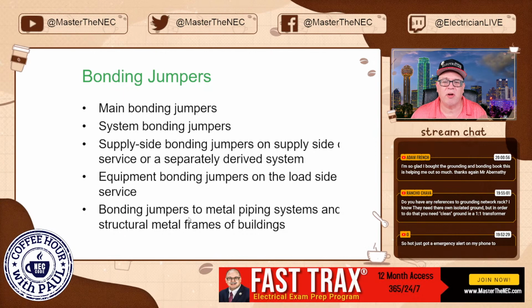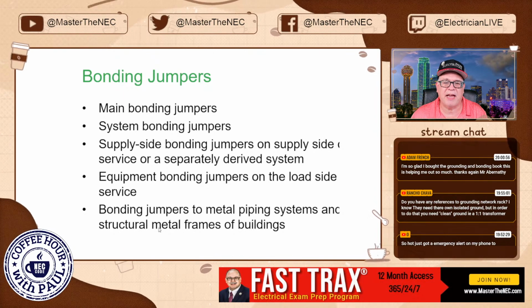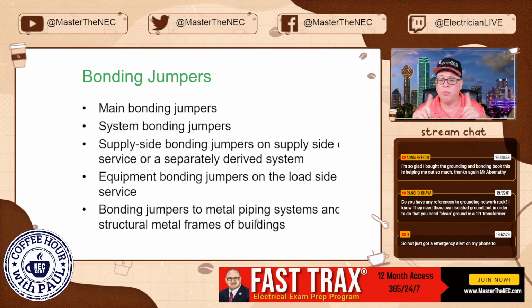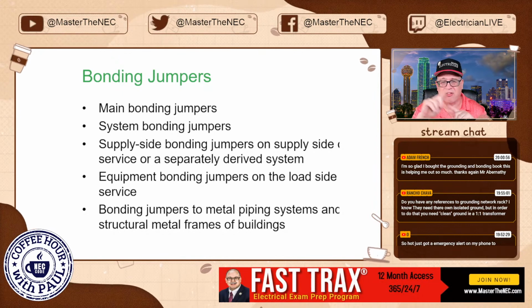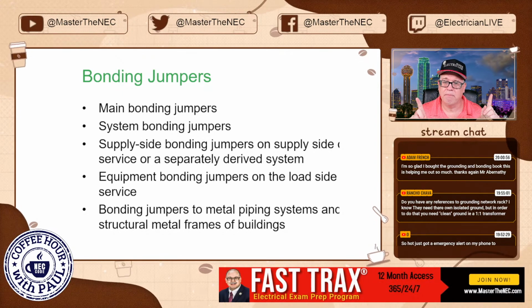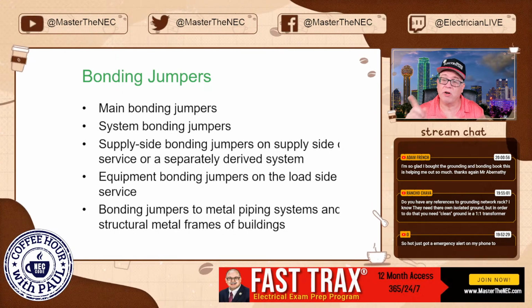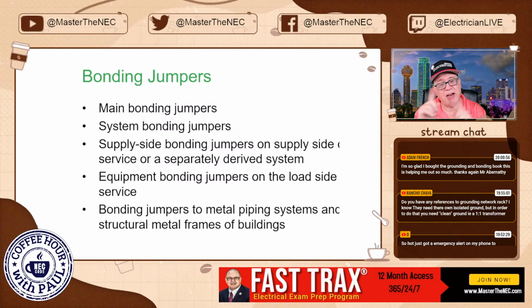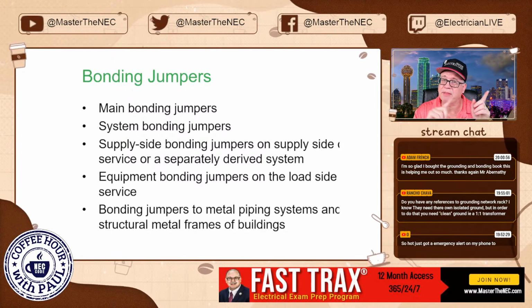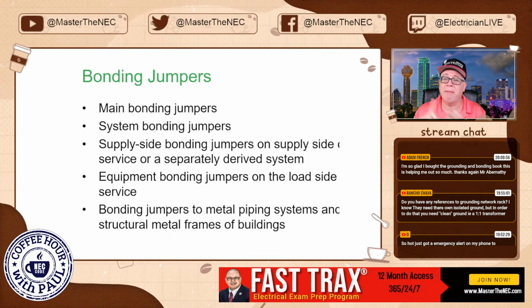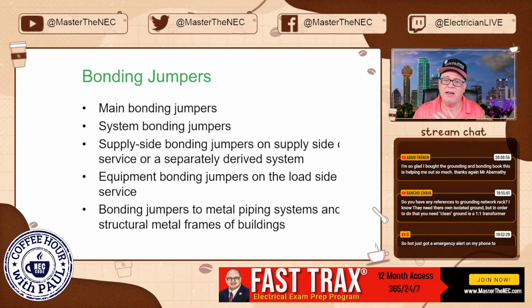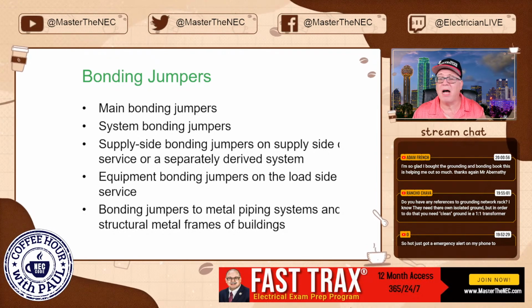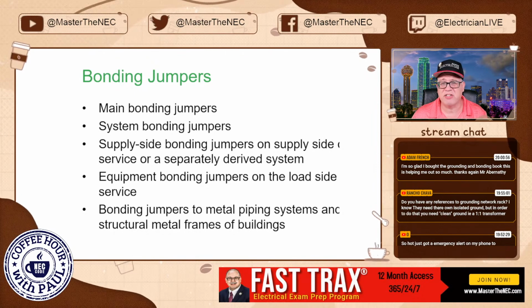And then you have bonding jumpers to metal piping systems and to structural metal frames. We have bonding jumpers that are simply tying systems together, okay? From one piping system to another piping system. From the metal frame of a building. Okay, all these type of things, those would be bonding jumpers. So you got main bonding, system bonding, supply side, equipment bonding jumpers, and then bonding jumpers in general that can tie things together. Okay.